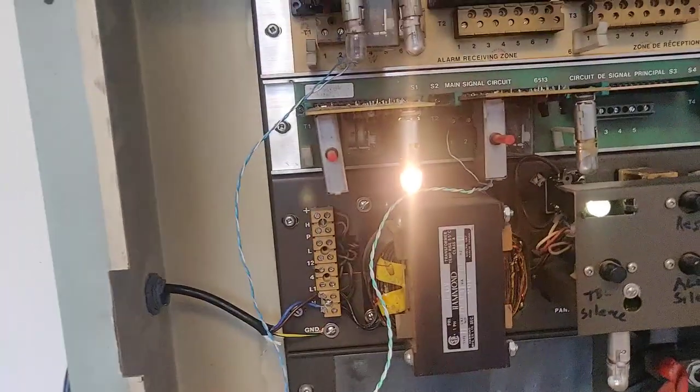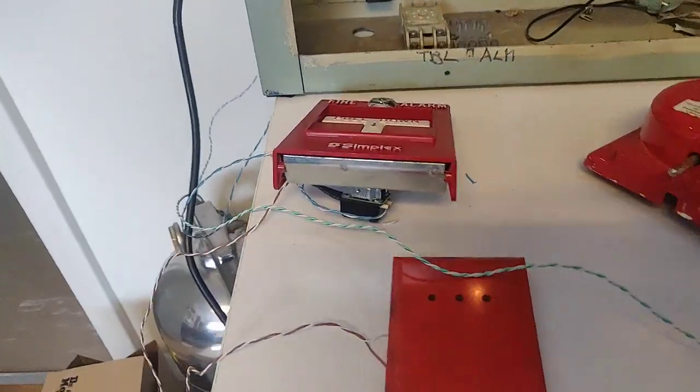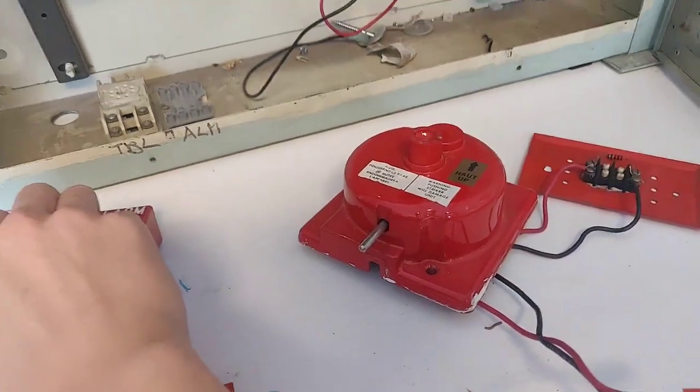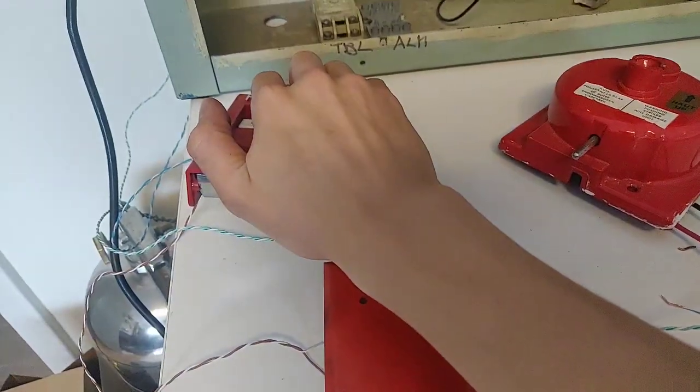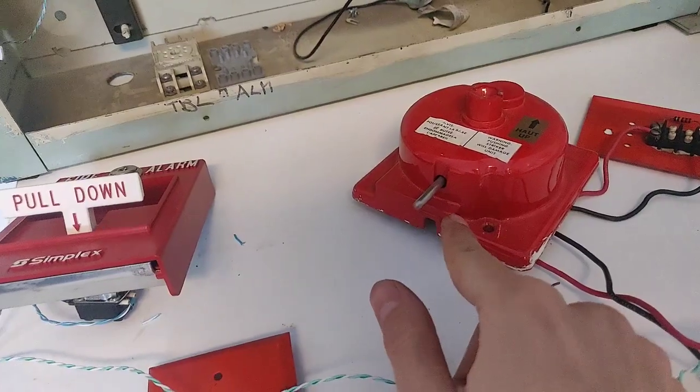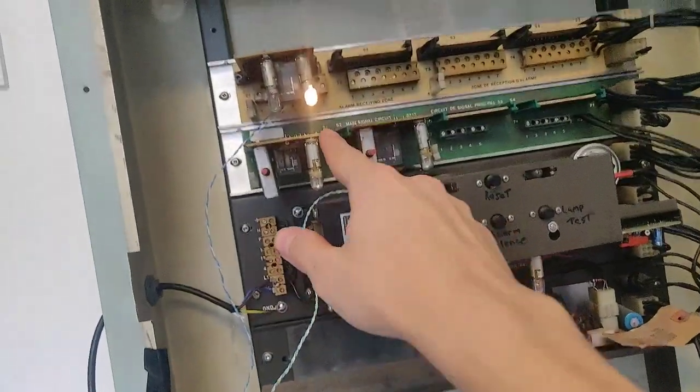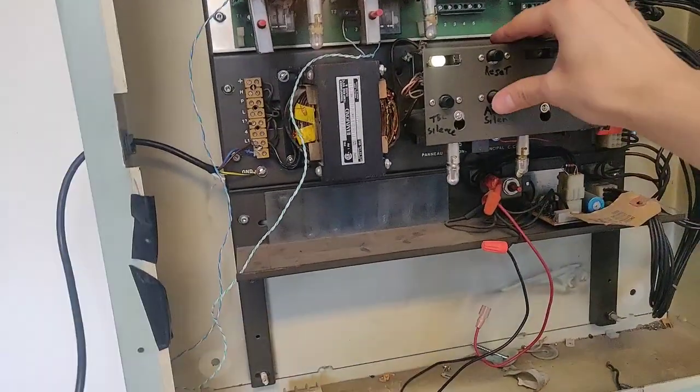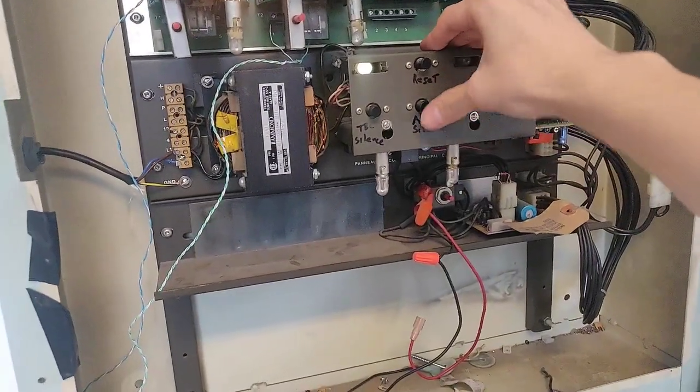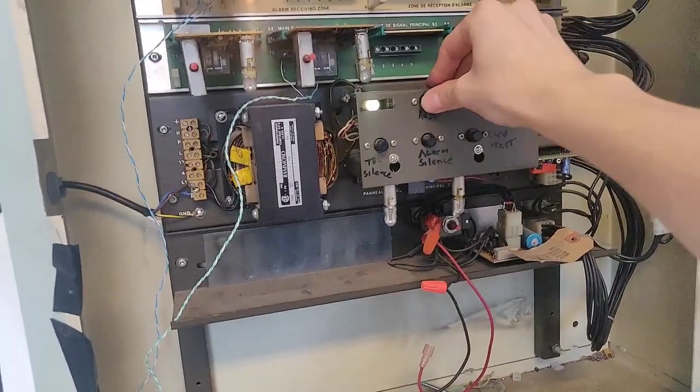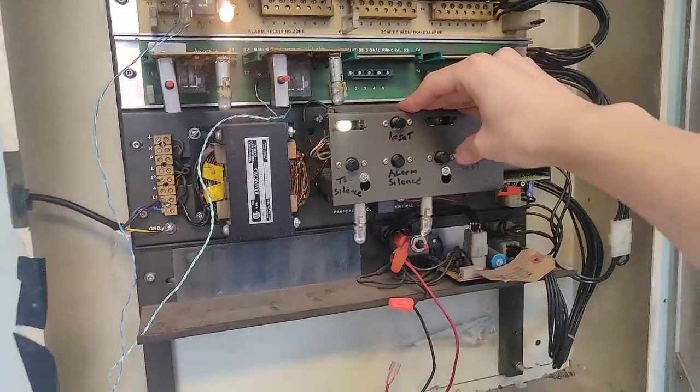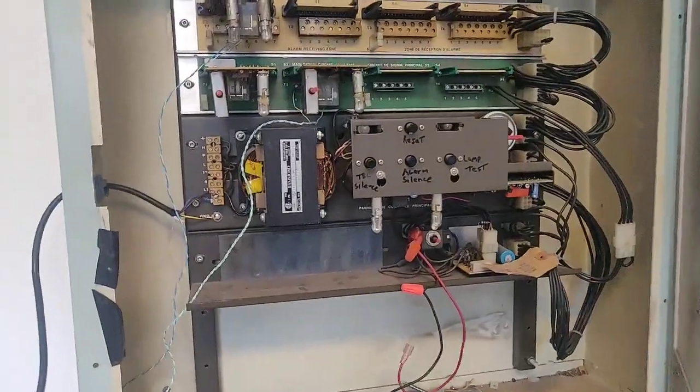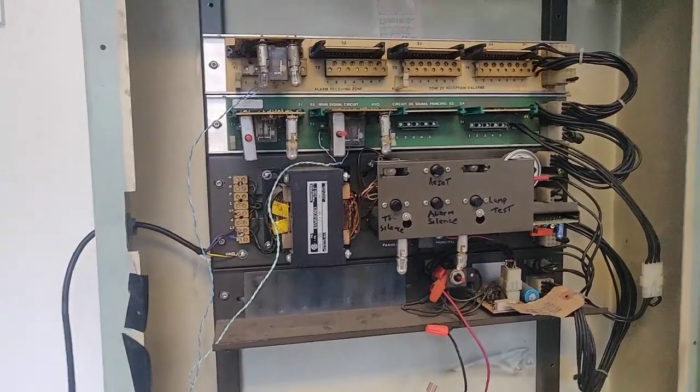So this one's in trouble because it's not actually hooked up to anything. But now we can see if we pull the pull station it will have this motor moving. I took off the gong so it won't be too loud. So you can see the alarm silence features aren't functioning.